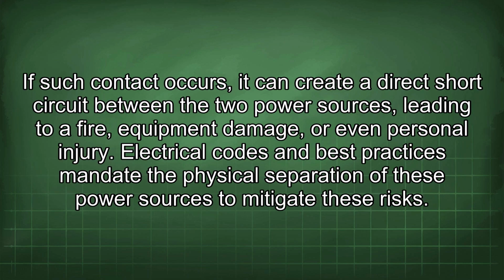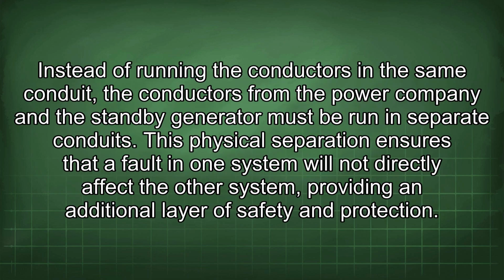If such contact occurs, it can create a direct short circuit between the two power sources, leading to a fire, equipment damage, or even personal injury. Electrical codes and best practices mandate the physical separation of these power sources to mitigate these risks. Instead of running the conductors in the same conduit, the conductors from the power company and the standby generator must be run in separate conduits. This physical separation ensures that a fault in one system will not directly affect the other system, providing an additional layer of safety and protection.